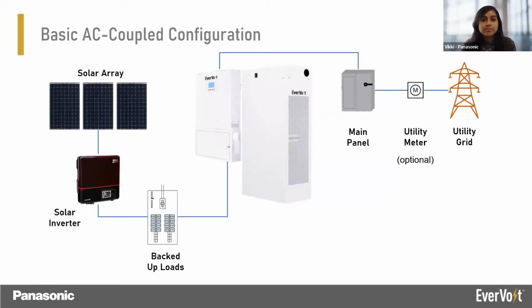Next slide, Bruce. This is a quick wiring diagram. Again, very, very simplified. We do have detailed engineering wiring diagrams available for our certified installers. But the configuration is fairly straightforward, where in an AC coupled solution, the solar array is connected to the backed up loads, and there is a load breaker, grid breaker, and battery breaker on the inverter's bottom access panel, which also ties into the grid and also connects with the battery. And for a single system, the bundle includes everything that's needed to achieve the basic single AC coupled configuration. However, in some cases, if the site requires CTs or other items, that is also provided by Panasonic.